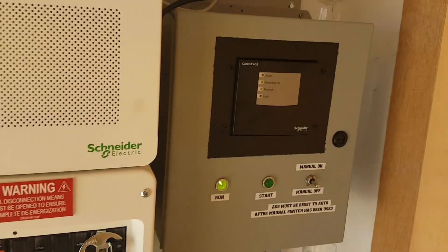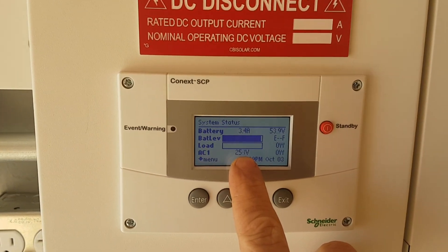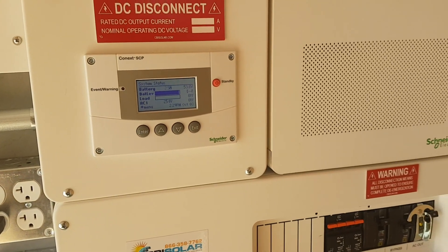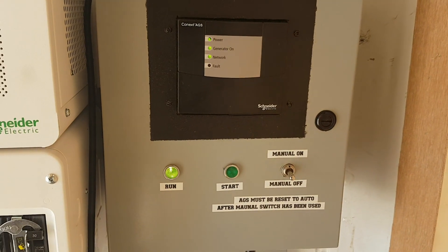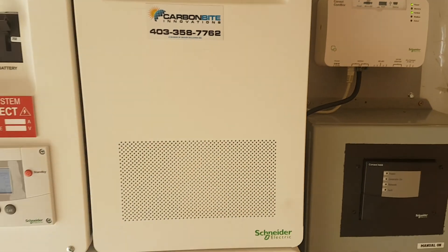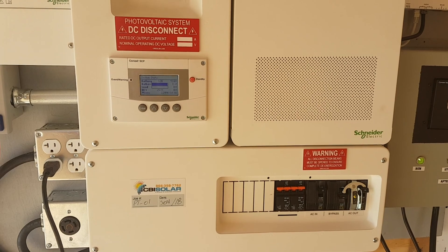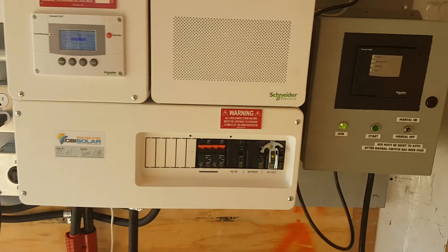There we go — generator cut out! It's in cool-down right now, so the generator is no longer powering the inverter — output is at zero, load is at zero. The generator will cool down for 30 seconds and then shut off. Kind of interesting — a watched pot never boils. Never thought that was true until today. There we go — generator on, generator off, no lights on.